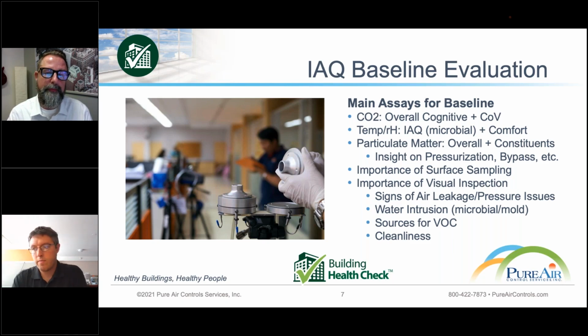Absolutely. One of the foundational pieces is always collecting your outdoor air, because mold is ubiquitous, as are a lot of other constituents. So we don't expect to see a sterile, perfect environment in nine out of ten buildings—there's going to be influence from the outside air. To avoid a false positive, we take that outside air in combination with visual things like pressurization of the building and looking at the filter racks and HVAC units, finding the areas where issues could occur. That gives us a layer of protection for understanding the building.